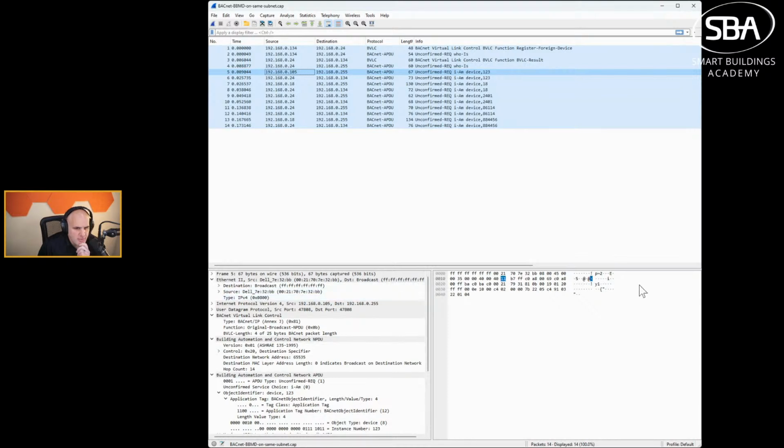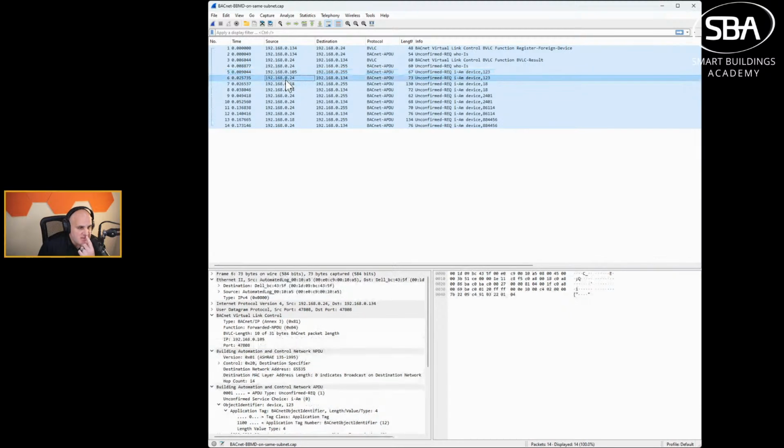Okay, so without having an architecture in front of me, what I think is happening in this, and remember, I am not the person who created this network, is that Dell is sending out the discovery broadcast, and Dell is getting the response from Automated Logic.